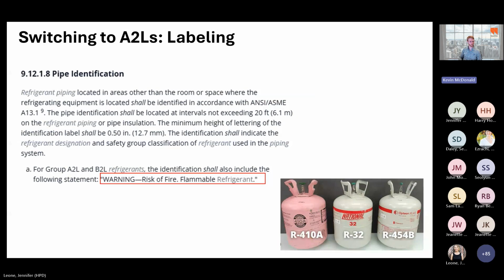There's one more slide here. Again, there are flammability considerations, so just labeling the piping periodically that it's a risk of fire, flammable refrigerant. There are a few other considerations from FDNY that weren't necessarily explicit in the ASHRAE 15 code, like grounding the condenser and grounding the equipment so there isn't a risk for ignition locally. There may be some other minor clarifications from FDNY or DOB that can be addressed in the Q&A session. These are not all of the requirements for A2Ls, but some of the major considerations that may affect planning overall for the project.